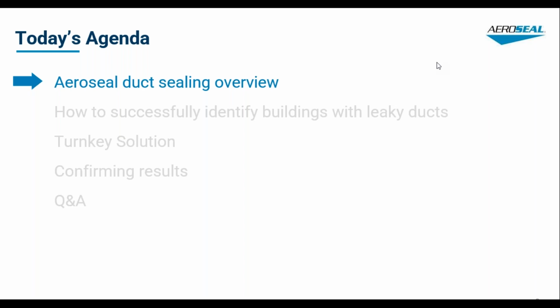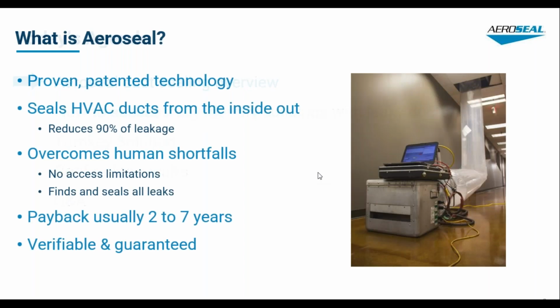So first, we're going to talk a little bit about Aeroseal duct sealing and what our process is. Just like we talked about in series 1, Aeroseal is a patented technology that seals up the HVAC ductwork from the inside out. Basically, we're pressurizing the duct and injecting an aerosol sealant that seals up all the holes and gaps. We typically get about 90 to 95% of the leakage sealed, and our payback is around 2 to 7 years on those projects. Like we're going to talk about later, it's both verifiable and guaranteed to you.